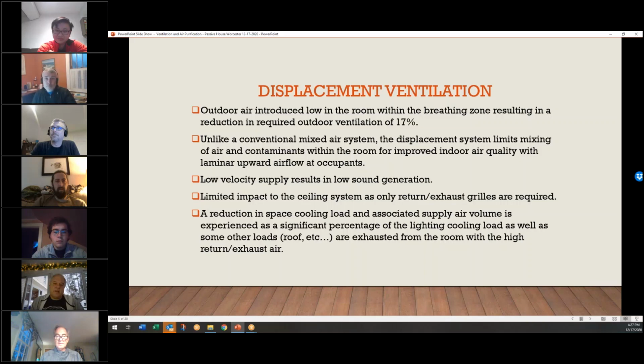So we tend to use that a lot in most of our high density classroom spaces. And again, you get your 17% benefit of lower outside air. Until recently, trying to be smart with CO2 demand reset and optimizing your amount of outside air was what everybody was trying to do to reduce energy costs. Of course, lately it's gone the reverse, where it's like, no, we want to run everything 24 hours a day. We want to have outside air and override all the CO2 resets. And that's what we're doing temporarily. But I feel that we're coming back to energy efficiency hopefully soon, because I know we've been burning a lot of power trying to ventilate these buildings lately.